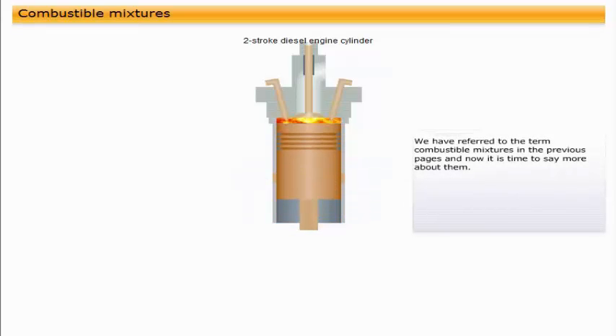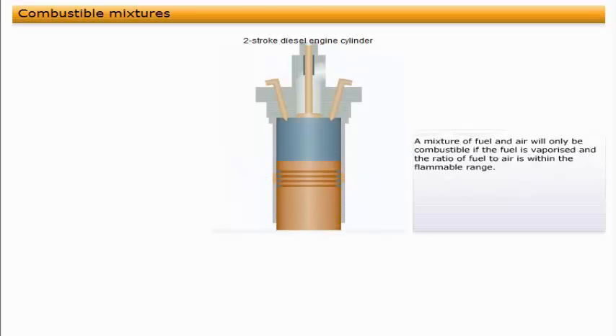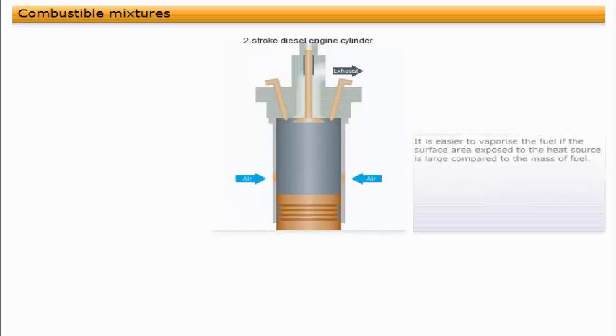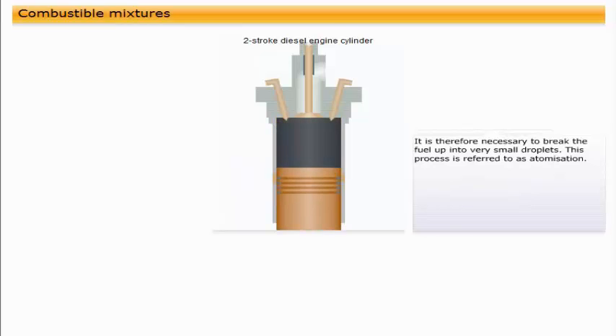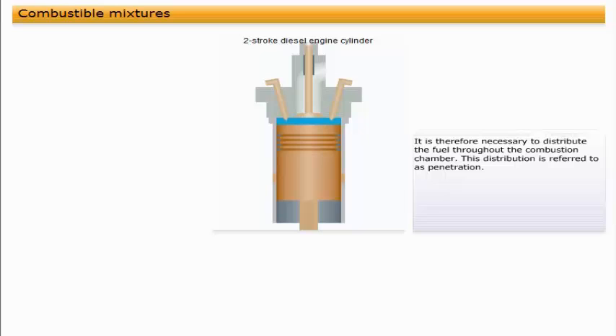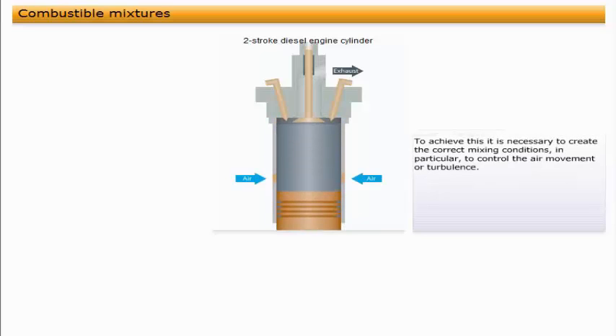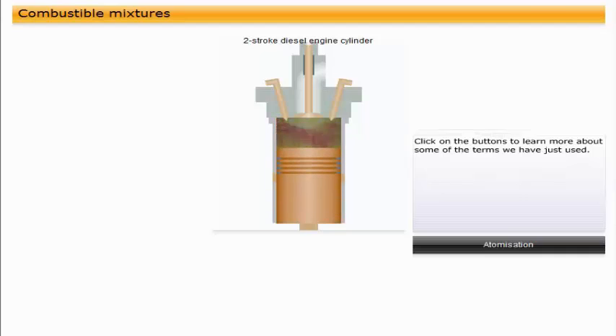We have referred to the term combustible mixtures in the previous pages, and now it is time to say more about them. A mixture of fuel and air will only be combustible if the fuel is vaporized, and the ratio of fuel to air is within the flammable range. It is easier to vaporize the fuel if the surface area exposed to the heat source is large compared to the mass of fuel. It is therefore necessary to break the fuel up into very small droplets. This process is referred to as atomization. In a diesel engine, it is desirable that the whole volume of the combustion chamber is used. It is therefore necessary to distribute the fuel throughout the combustion chamber. This distribution is referred to as penetration. The fuel and air must be mixed so that the fuel and oxygen are evenly distributed to ensure that combustion is as complete as possible. To achieve this, it is necessary to create the correct mixing conditions, in particular to control the air movement or turbulence.